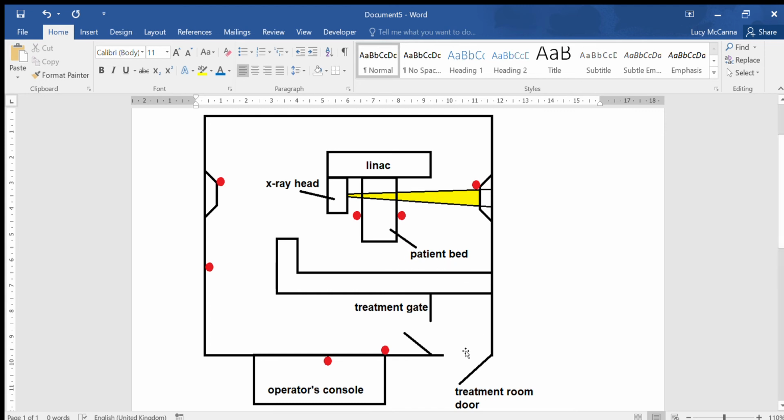There will be one, the first one you would see, visible from when you move into this door, and if the light is on, the LINAC is on. That's an immediate visual thing to tell you this dangerous equipment is operating now, and that's done with a light.